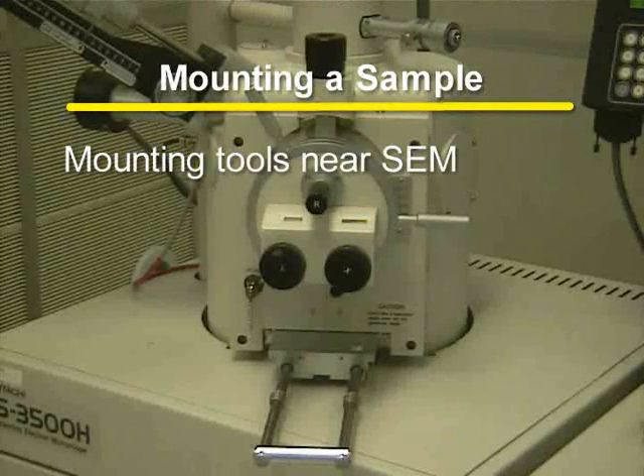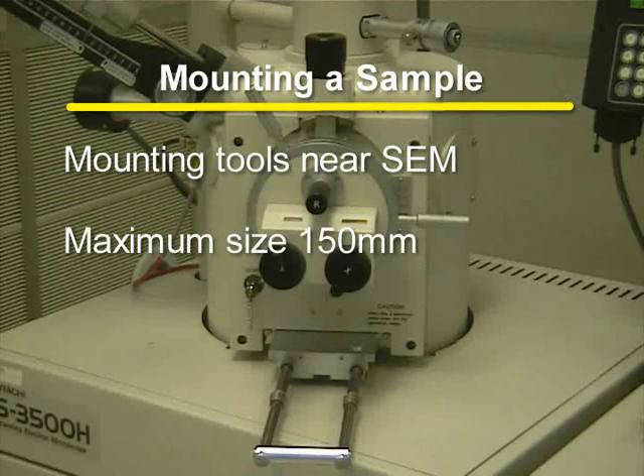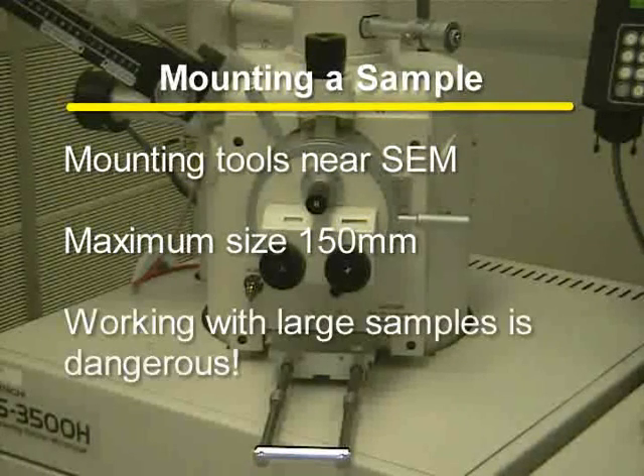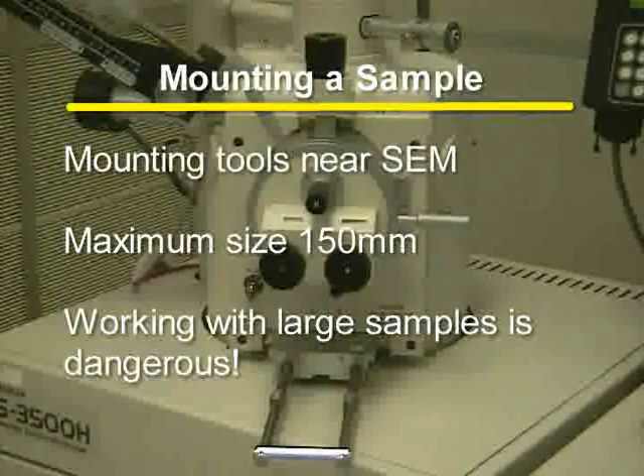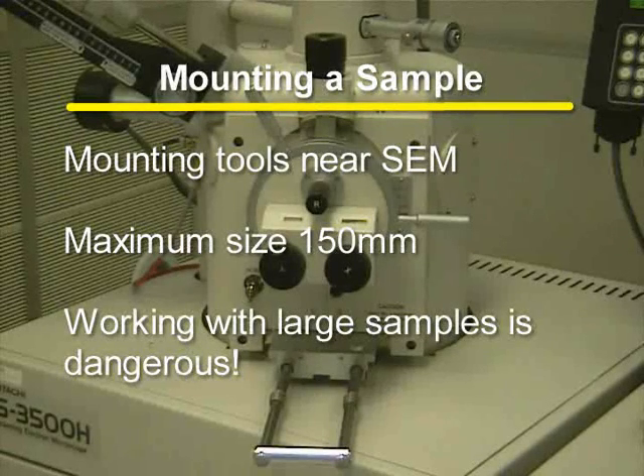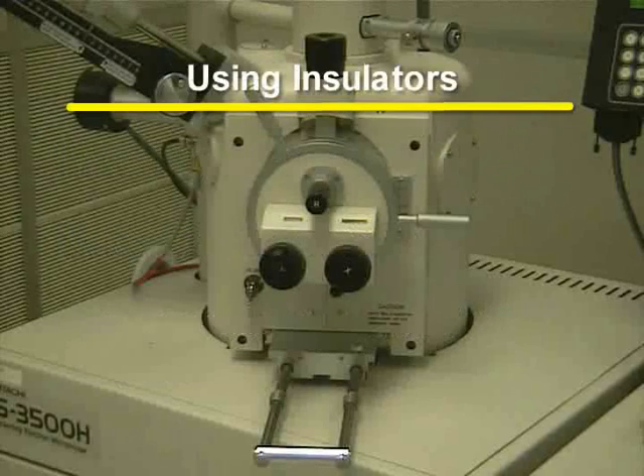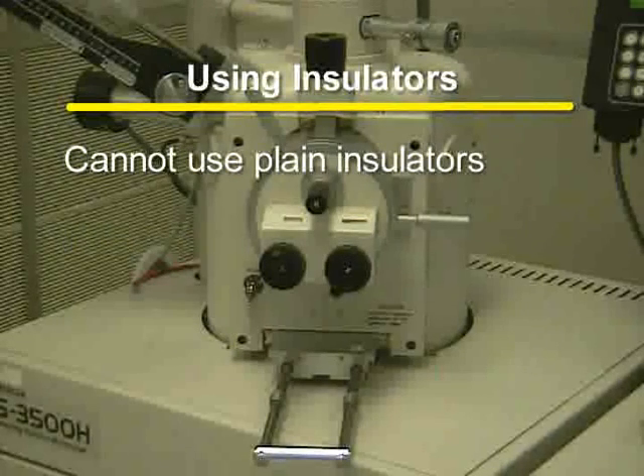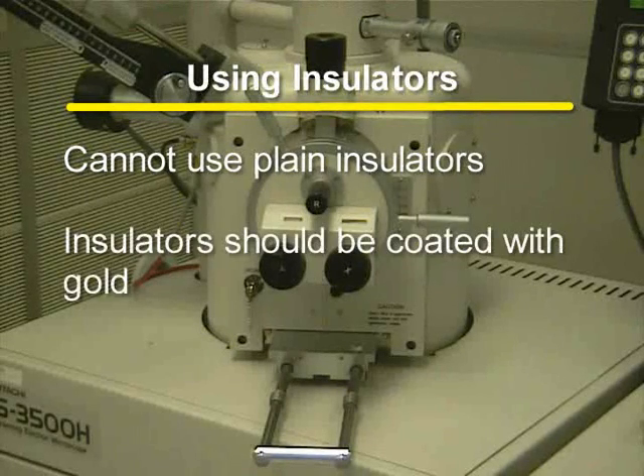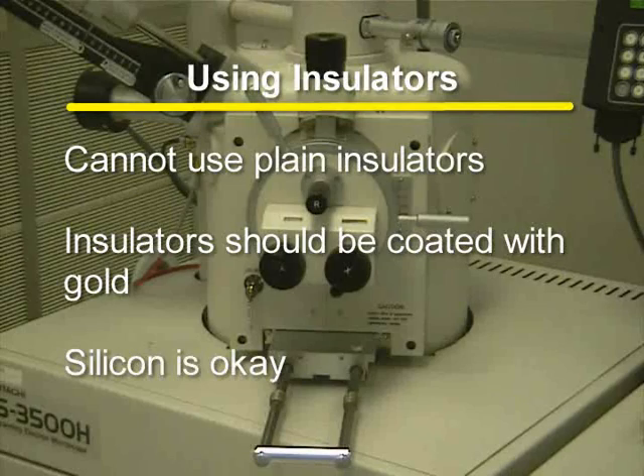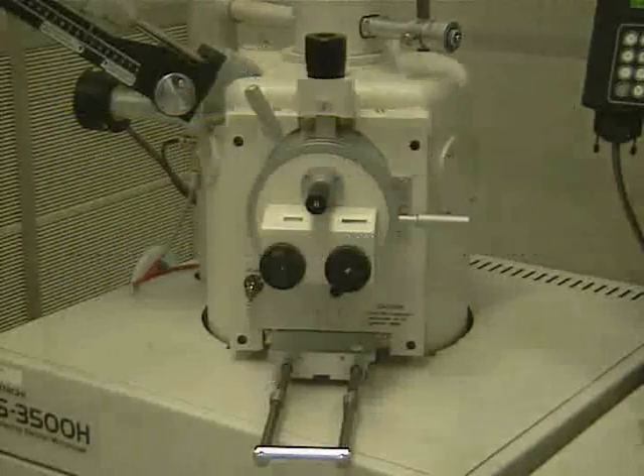Mounting samples will be located in a plastic box near the SEM. You can mount samples of all different sizes, with the maximum size being 150 millimeters in diameter. As stated before, remember that working with large samples greatly increases the risk of crashing the sample into the lens. The sample that you use in the SEM cannot be an insulator. If the sample is an insulator, it must be coated with gold using the gold sputter coater. Silicon is okay to use in the SEM. We will show the effects of using an insulator later on in this video.